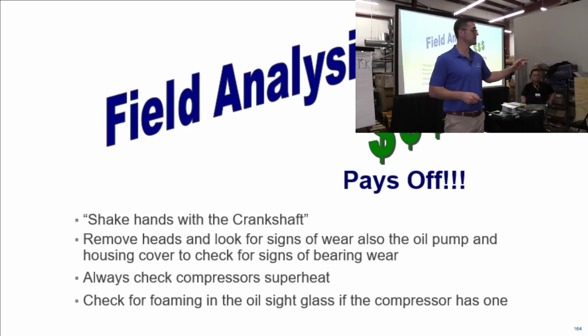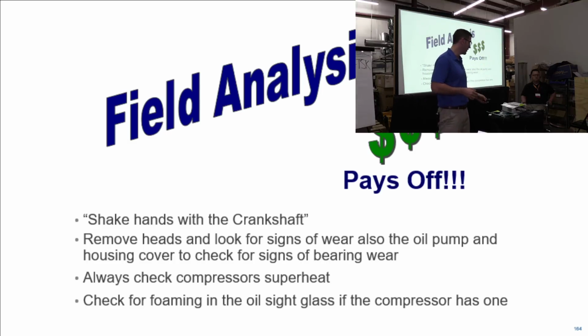Okay. One thing I didn't talk about. Semi-hermetic compressors. One of the checks, and we're going to go through this today, what I'm going to get you guys to do, you're out in the field, you want to ohm out the compressor to see if it's electrically failed. You want to take off the head, inspect the gasket. That's what we're going to do, and I'll say this over again. Inspect the valve plate. Look inside the cylinders. See if they pump. Pull off the pump.